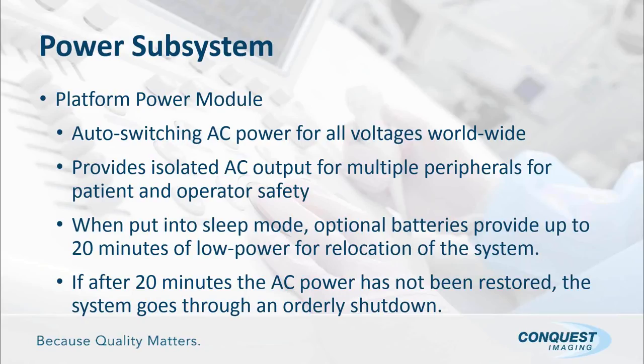It also allows you to put it into sleep mode. Obviously, this is if it has optional batteries, which we'll discuss a little bit more. But these optional batteries give you 20 minutes of life where the system can be in the sleep mode we described earlier and allow you to transport it from one room to another, from one floor to another. The really nice thing about this is if you're using these batteries, after the 20 minutes, it doesn't just kill the system. It allows the system to go into an orderly shutdown mode, as if it was asked to do so.